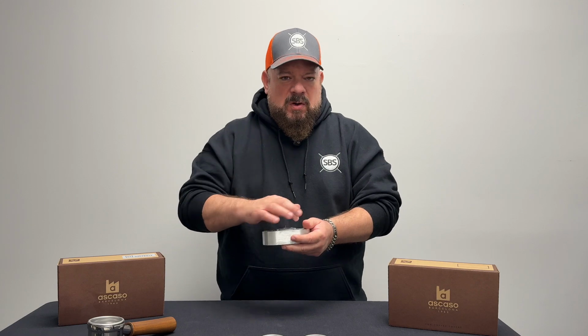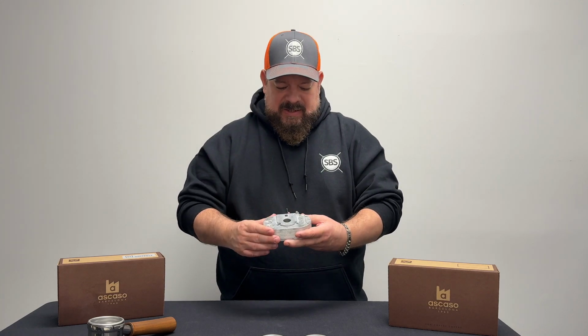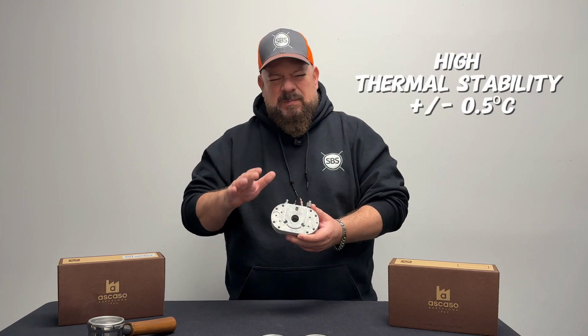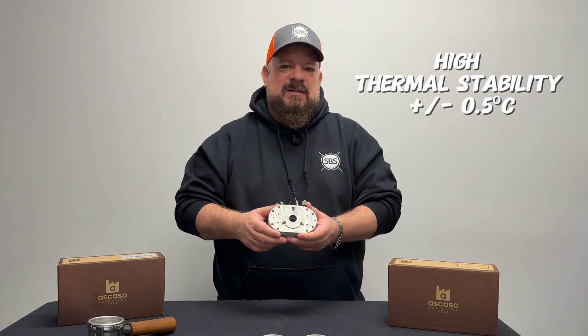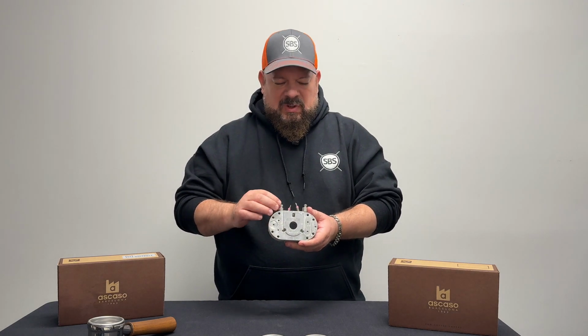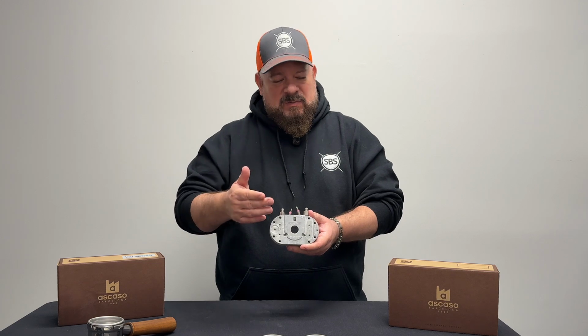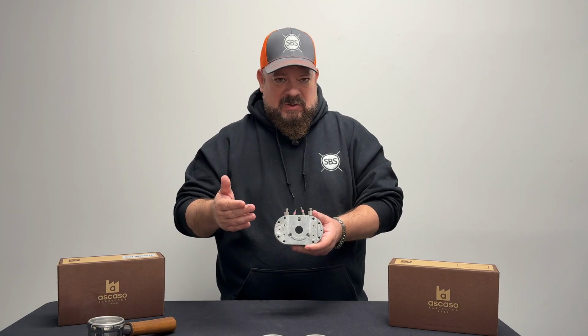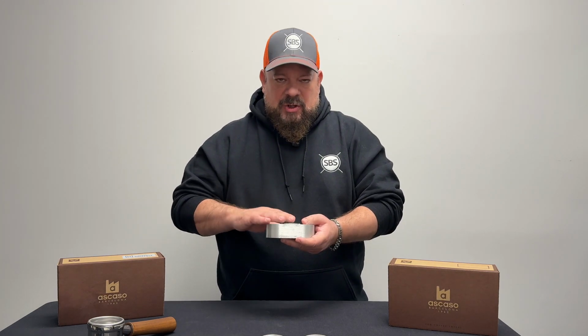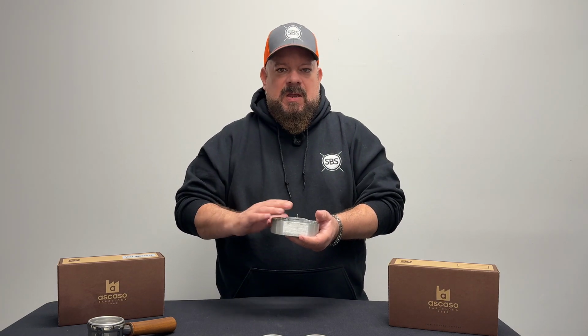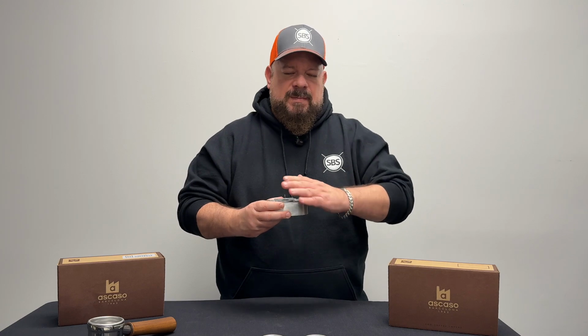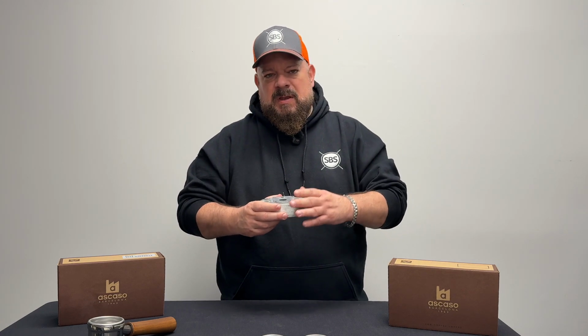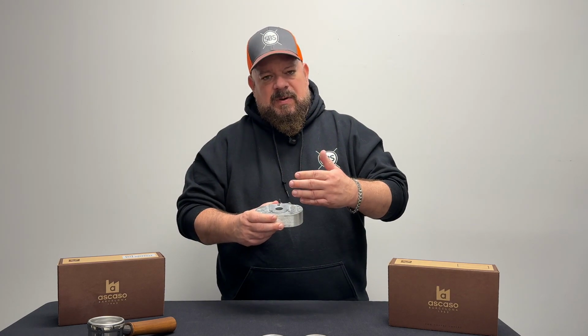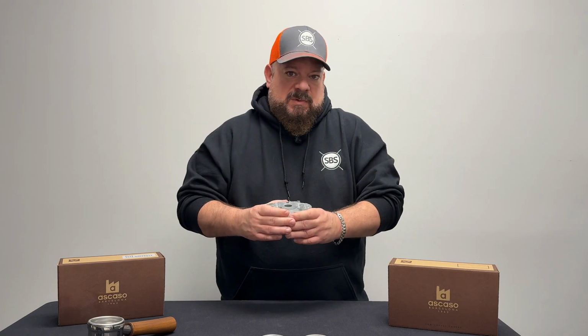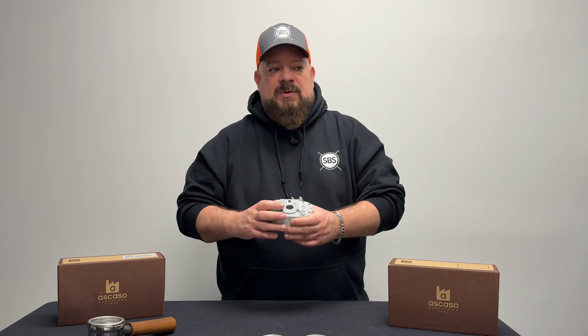What this gives you with all of that 1 meter of tubing inside here is an extremely consistent plus or minus 0.5 degree Celsius in water temperature. It gives you limescale resistance, because stainless, as we all know, is much more resistant to any corrosion. Should the water be cut off to this thing, we're not going to have an element problem. We're just heating the block, so we're just keeping the block warm. So that's the beauty of this. Should there be a problem internally or a plugged pipe of water, this will just stay warm, so it actually won't plug up, which is a wonderful thing.